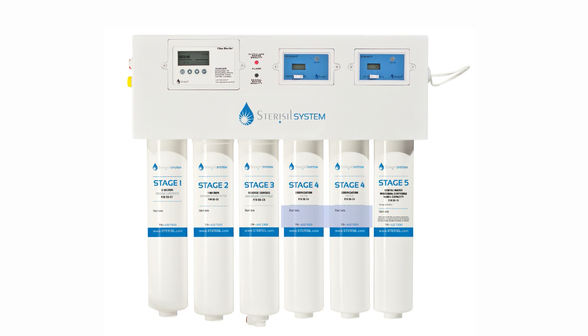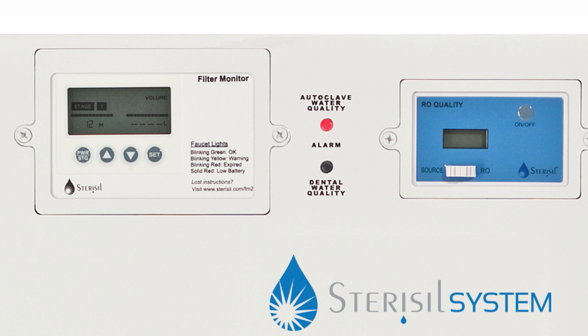After replacement, record the installation date onto the label of the new stage 4 cartridge. A new stage 4 cartridge will typically last 3 months to 1 year, depending on the volume of water used and the quality of the source water. The LED light and alarm should automatically reset when the new cartridges have been installed. The Sterisil system will actively monitor dental water usage. The dental water quality LED on the faceplate of the system will flash in 3 stages: first green, then yellow, then finally red when water is actively being used to indicate when the Stage 5 will need to be replaced.